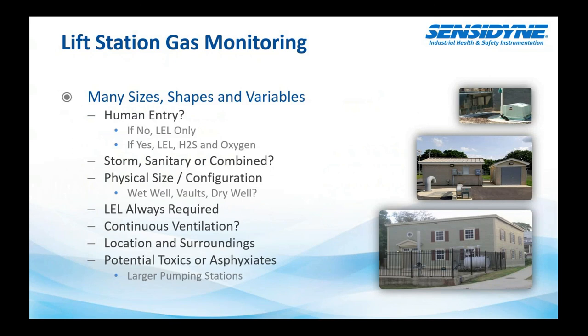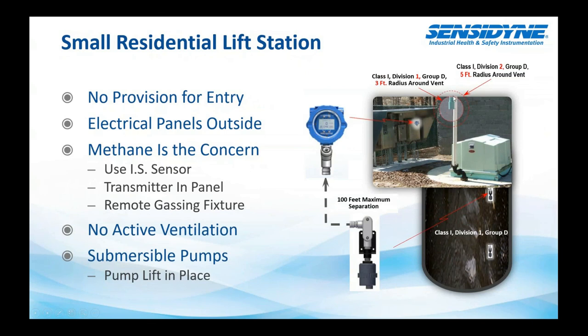Just some examples of lift stations. Lift stations come in many different sizes, shapes, and variables. Some will have human entry, some won't, mostly probably don't, unless they're very large lift stations, other than maybe a ladder to go down into the well to service pumps and things like that. These can be storm or sanitary or combined. You'll always want to monitor for LEL because of the methane gas, and some may have some ventilation, if that's possible as well. And some you might want to monitor the surrounding areas because, in this example here, you have the vents. So if there were issues with a surrounding neighborhood or something where you want to make sure this was not causing a problem, you could monitor for that.